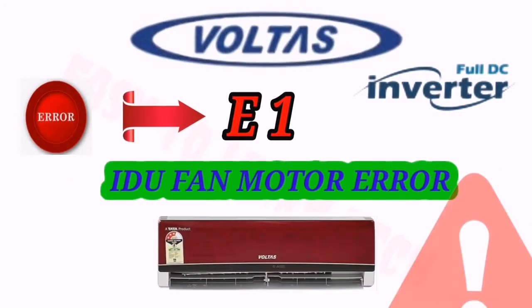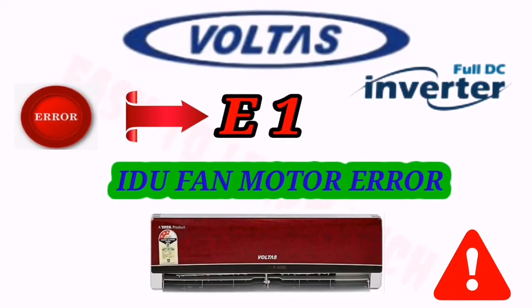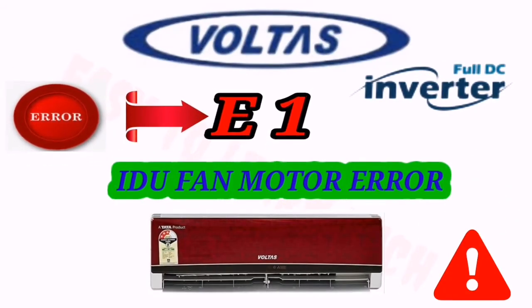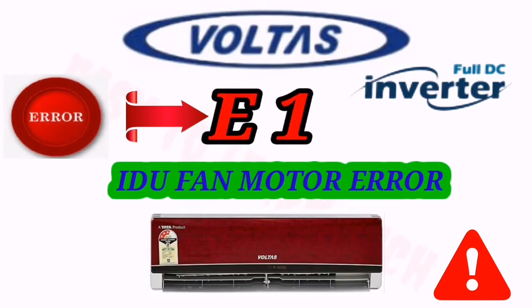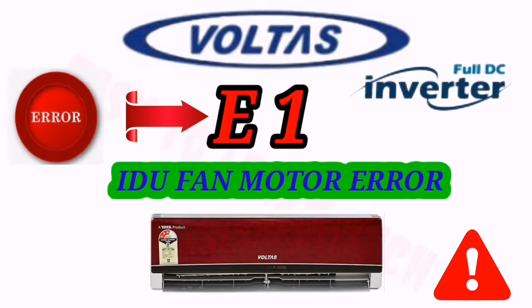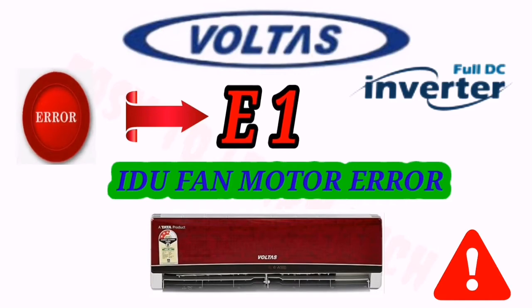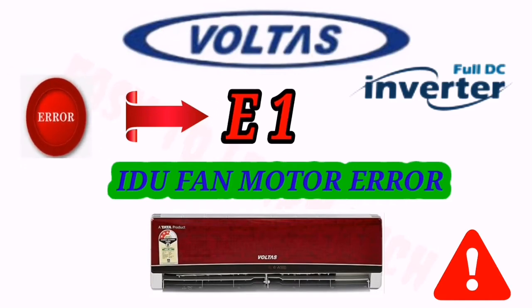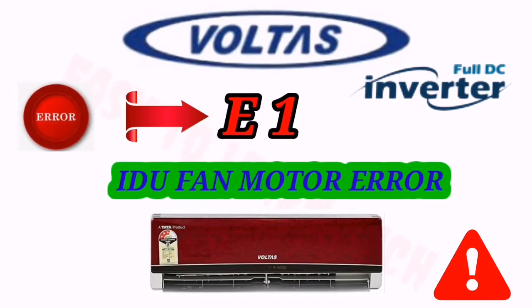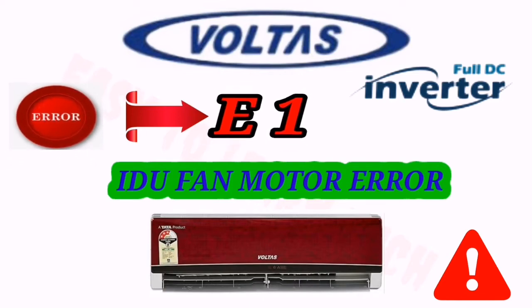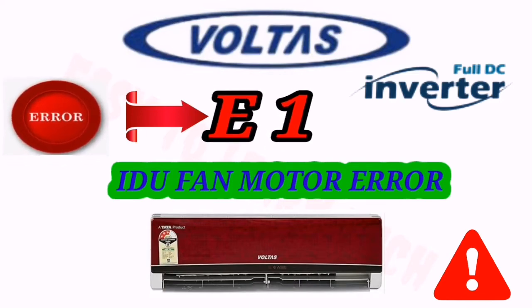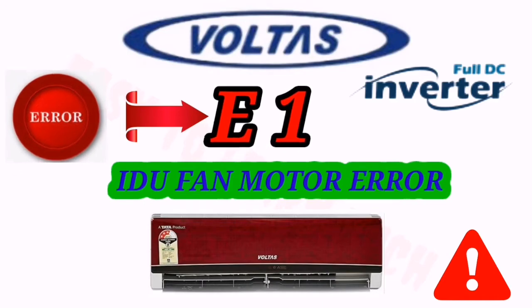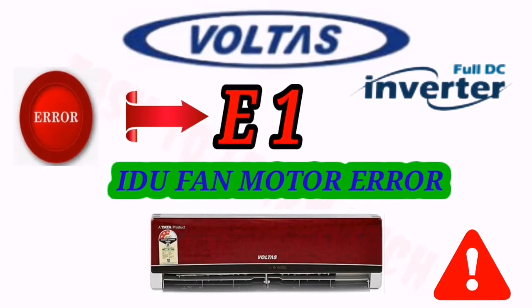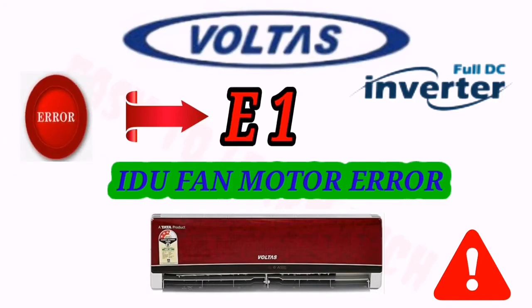Let's see the next error code. When you see E1 on your display, it means indoor fan motor faulty. First of all, you have to check the position of the motor, whether it is properly installed or not. Then you have to check the blade and the blower, and if the blower is getting stuck somewhere, you have to release it and make it free. You also have to check the connection on the indoor PCB, and if it's not properly connected, connect it properly and start the unit.